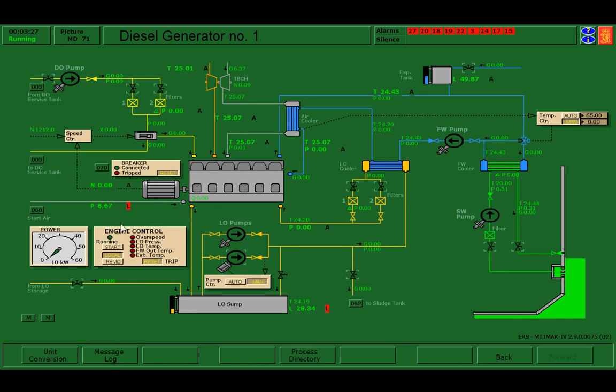Coming to this page, I can see right now I have a couple of alarms. So I have a low pressure on my air system, but I know that's filling, so that should be okay. I notice I have a low alarm on my lube oil, so I could add some lube oil to clear that alarm. Looks like my alarm just cleared, and I would make sure that I turn off my lube oil supply valve.